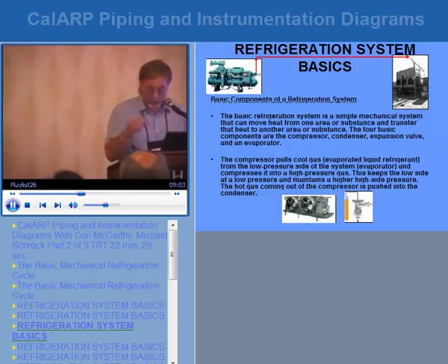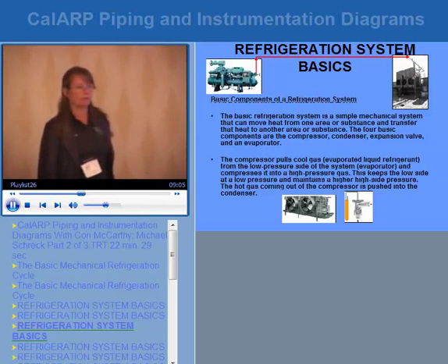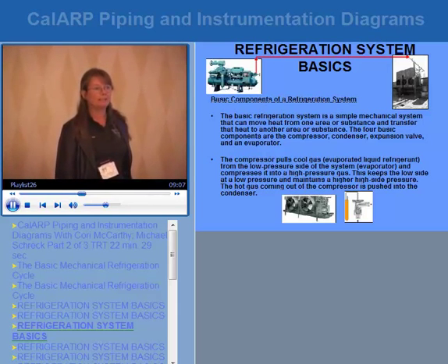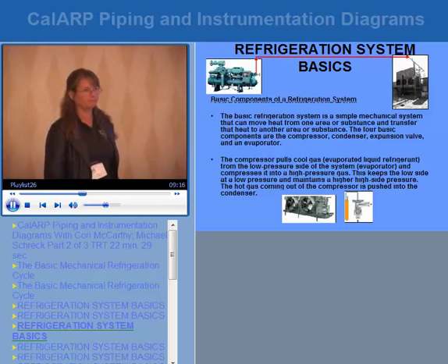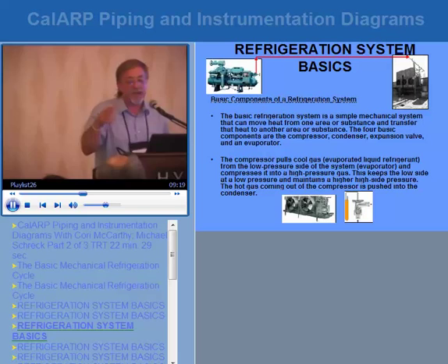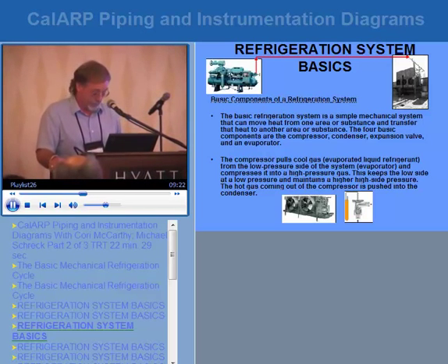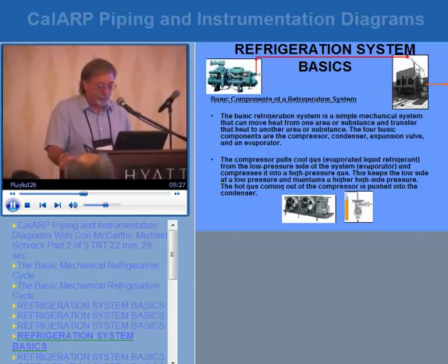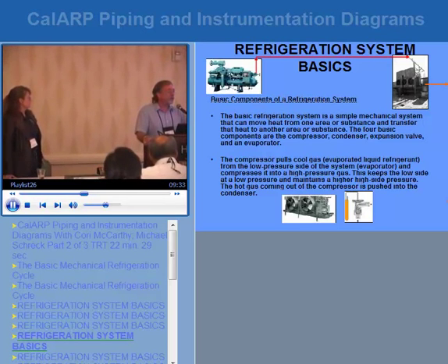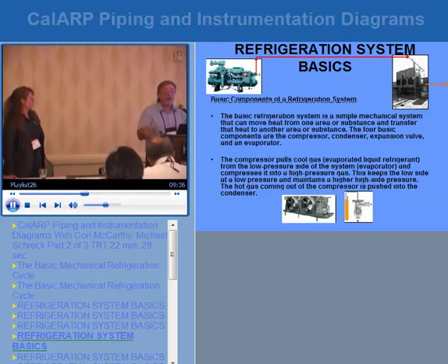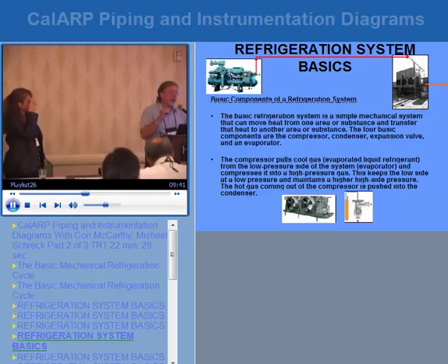Sometimes you'll see a sign near the high-pressure receiver called 'queen valve,' used either for the main hot gas line out of the high-pressure receiver or for the drain from the condenser — it can be confusing. Ask them and make sure they know what it means in their system. Typically from the high-pressure receiver we go out to the process — chillers, evaporators — where we absorb the heat. At minimum, operators should know how to zone-isolate those components, because that's where the exposure is going to be, where the production worker is, and where the product is.